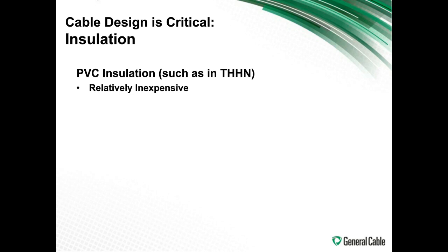So the cable design is critical. We need to look at the insulation. PVC insulation is what is used for THHN cables. THHN cables were predominantly used for the older style drives, and they were completely fine with those drives because of the older technology. The newer technology does not allow you to use them. So PVC, why is it good? Well, it's relatively inexpensive. It's flame retardant. It's easy to strip, flexible.